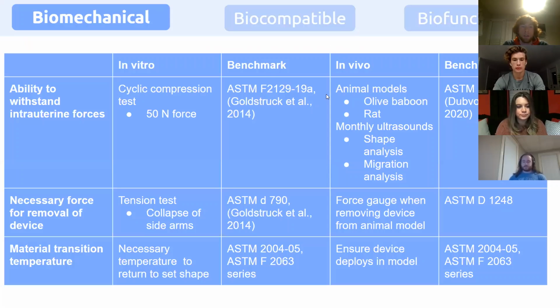In order to ensure that our device meets these engineering criteria, we will run a series of biomechanical, biocompatible, and biofunctional tests. The first biomechanical test will be the ability of the device to withstand intrauterine forces. We will test this in vitro using cyclic compression with 50 newtons of force, which is the max force that the device will experience in the uterus.